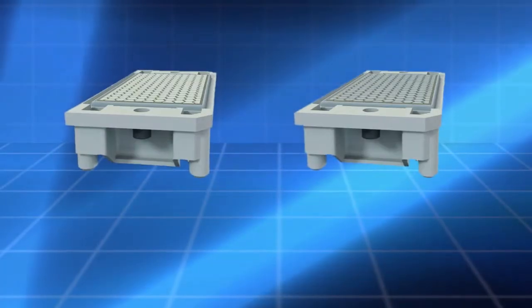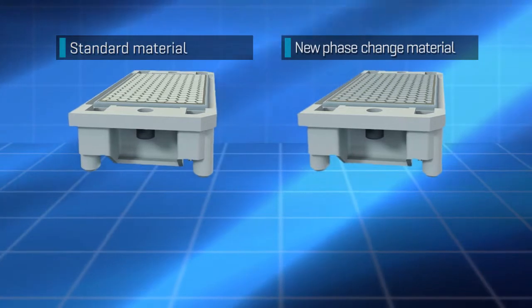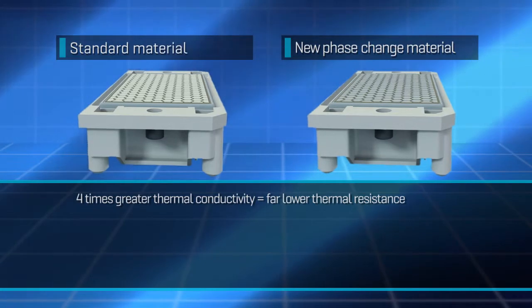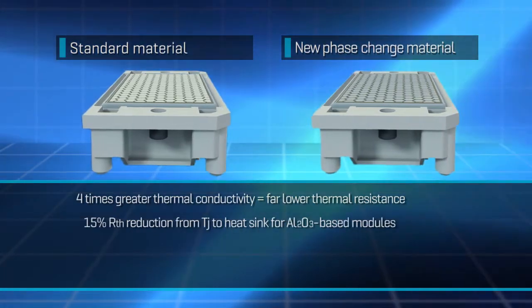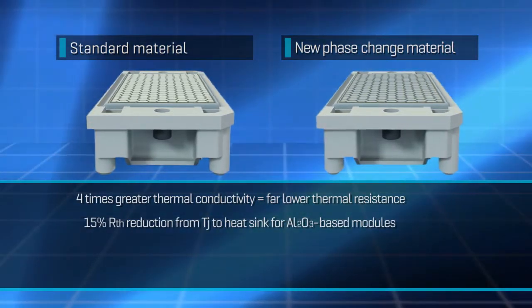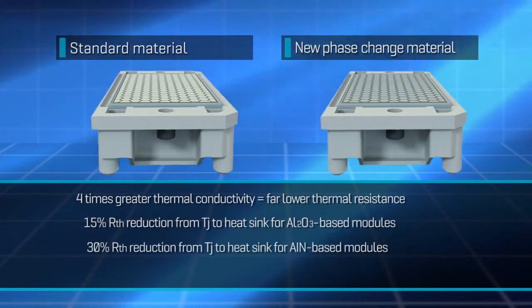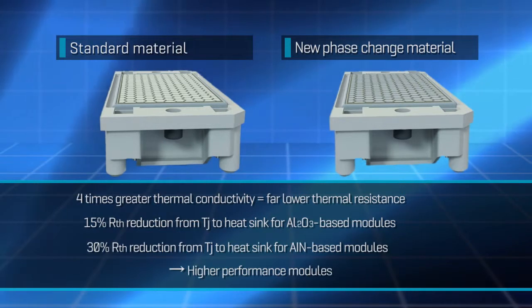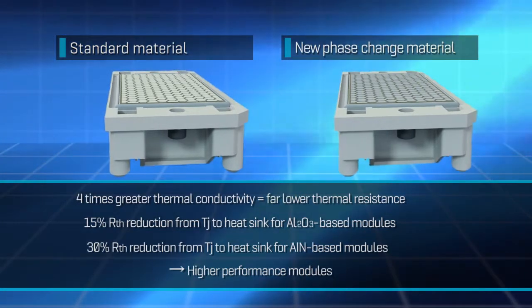Vincotech has also introduced a highly conductive thermal interface material based on phase change technology. This new material's thermal conductivity is four times greater than that of standard grease, reducing thermal resistance markedly — by 15% between the chip and heat sink in aluminum oxide base modules, and by around 30% in aluminum nitride base modules. The improvement in performance is equally dramatic.